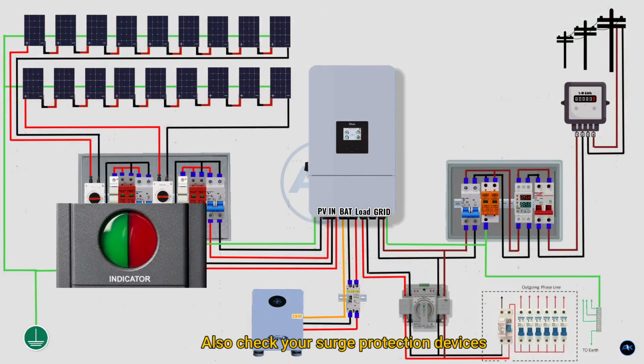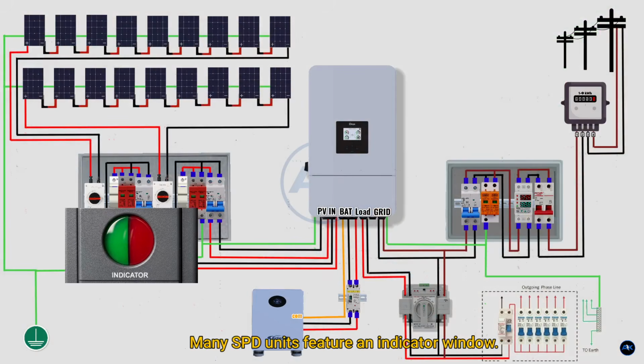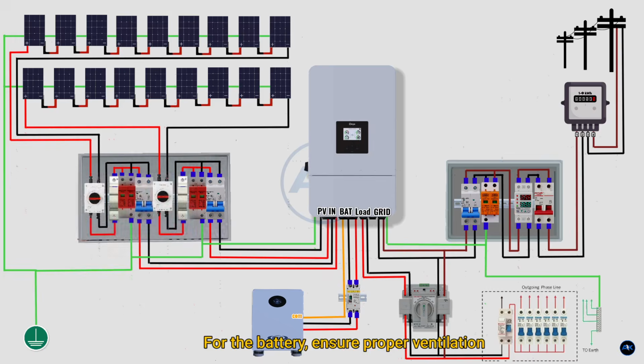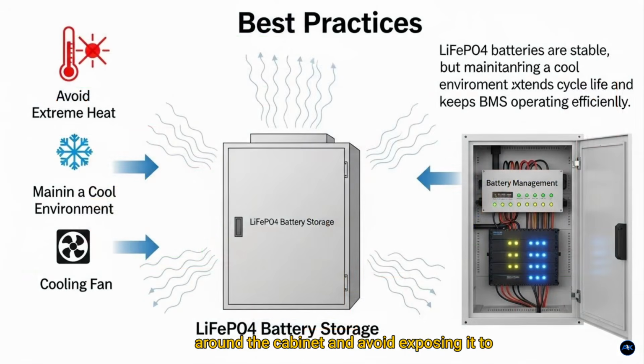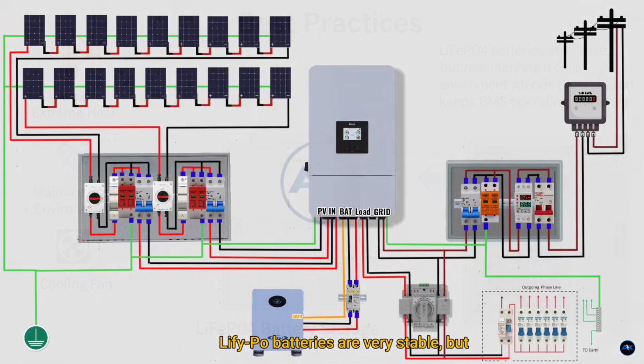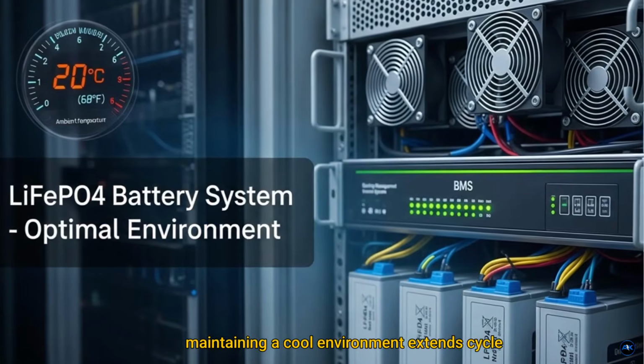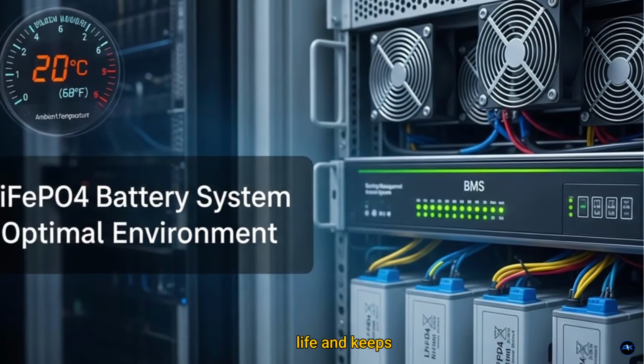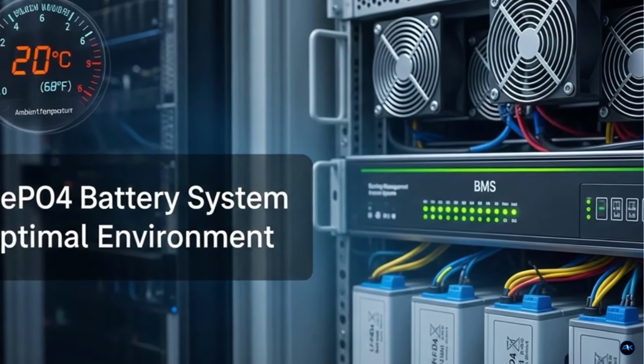Also check your surge protection devices periodically. Many SPD units feature an indicator window. If the color changes from green to red, the device has absorbed a surge and must be replaced immediately to maintain system safety. For the battery, ensure proper ventilation around the cabinet and avoid exposing it to extreme temperatures. LiFePO₄ batteries are very stable, but maintaining a cool environment extends cycle life and keeps the BMS operating efficiently.